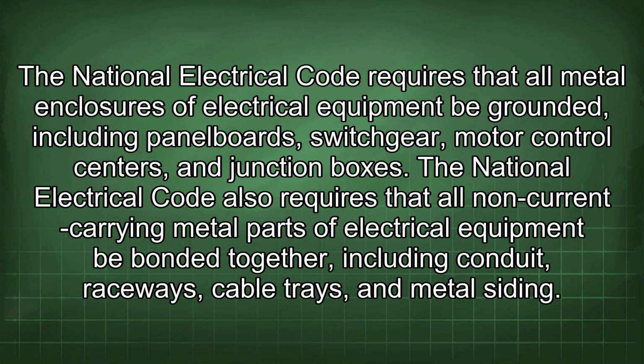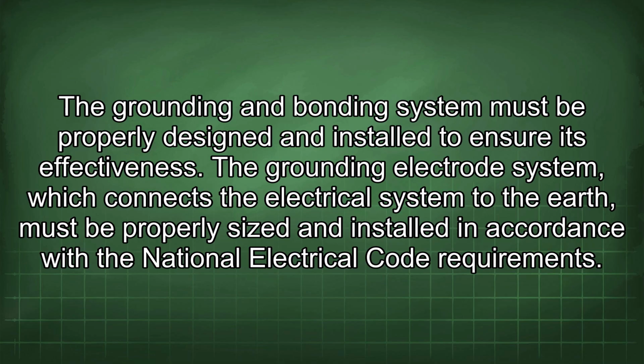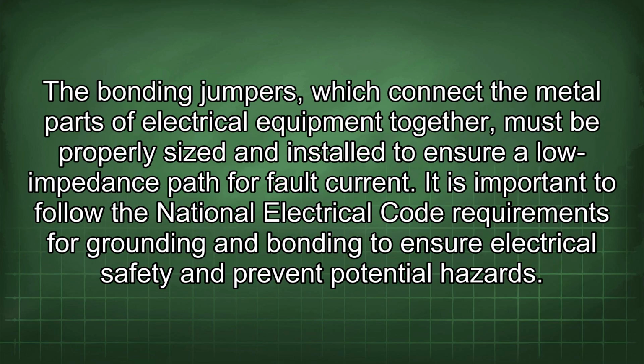The National Electrical Code requires that all metal enclosures of electrical equipment be grounded, including panel boards, switchgear, motor control centers, and junction boxes. The National Electrical Code also requires that all non-current carrying metal parts of electrical equipment be bonded together, including conduit, raceways, cable trays, and metal siding. The grounding and bonding system must be properly designed and installed to ensure its effectiveness. The grounding electrode system, which connects the electrical system to the earth, must be properly sized and installed in accordance with the National Electrical Code requirements. The bonding jumpers, which connect the metal parts of electrical equipment together, must be properly sized and installed to ensure a low impedance path for fault current. It is important to follow the National Electrical Code requirements for grounding and bonding to ensure electrical safety and prevent potential hazards.